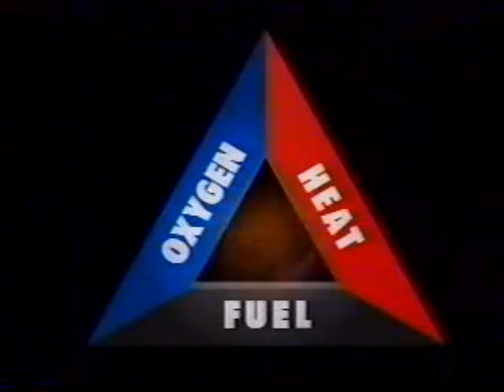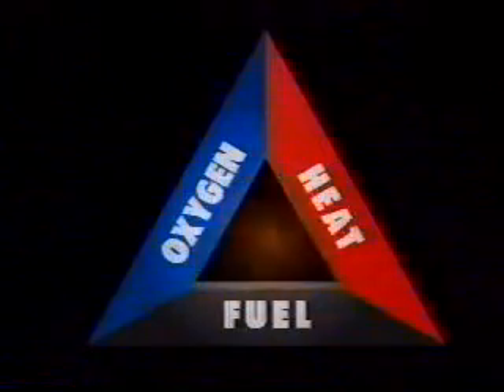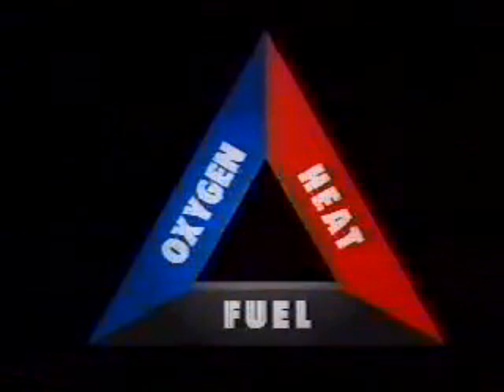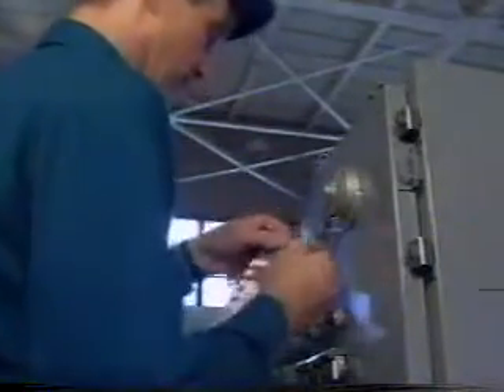Regardless of the type of fire, the goal of all fire prevention efforts is to separate or control heat and fuel sources. Here are some things to be aware of in the workplace. To begin with, it is vitally important that the work site heating system be kept clean and in good working order. This includes all pipes, switches, filters, wiring, and boiler controls. Since overheating of electrical equipment is also a major problem area, the use of automatic circuit breakers and overcurrent relays may be used. As an added safety factor, all facilities should use proper lockout-tagout procedures when testing circuits. Remember, only qualified personnel should troubleshoot or repair electrical circuits.